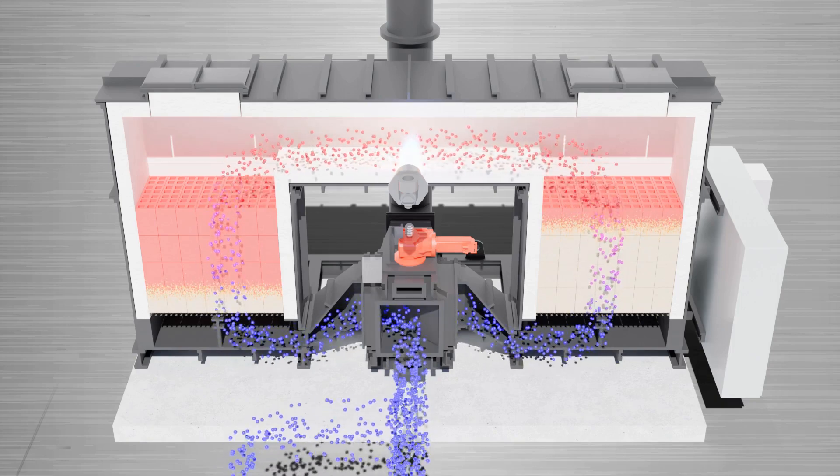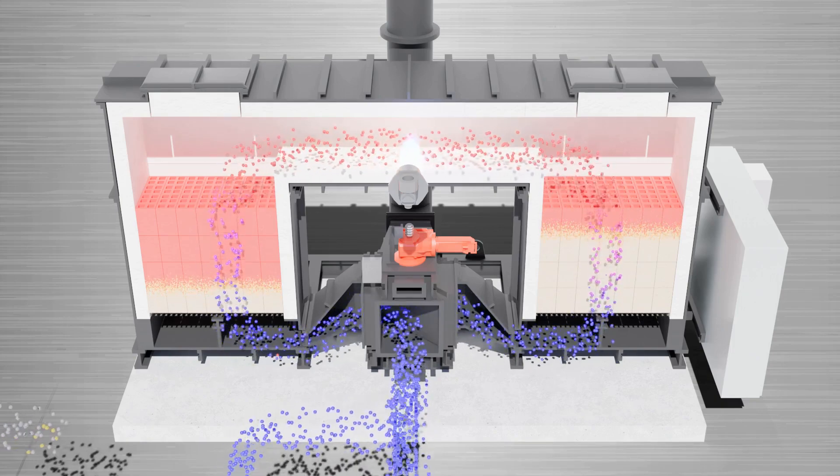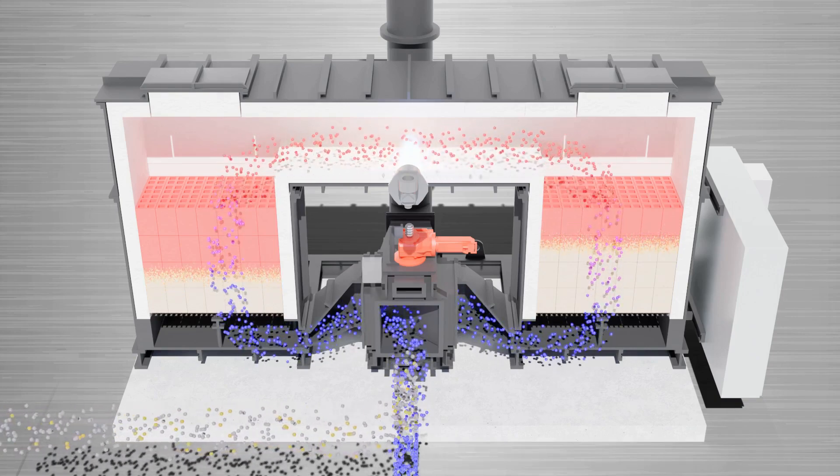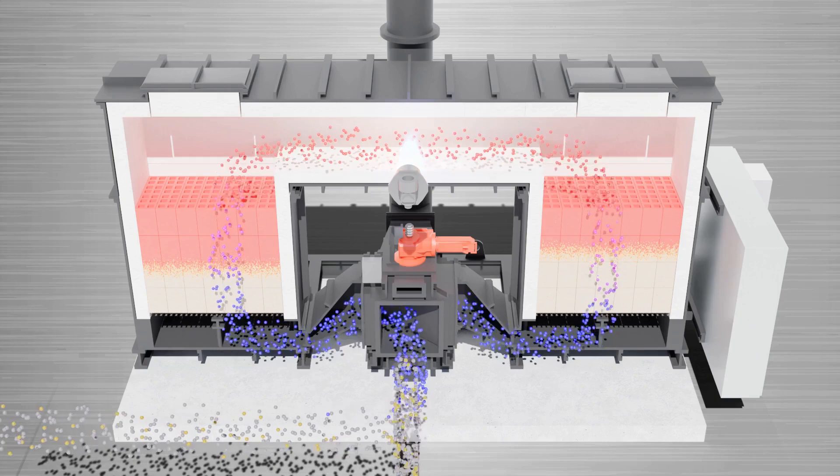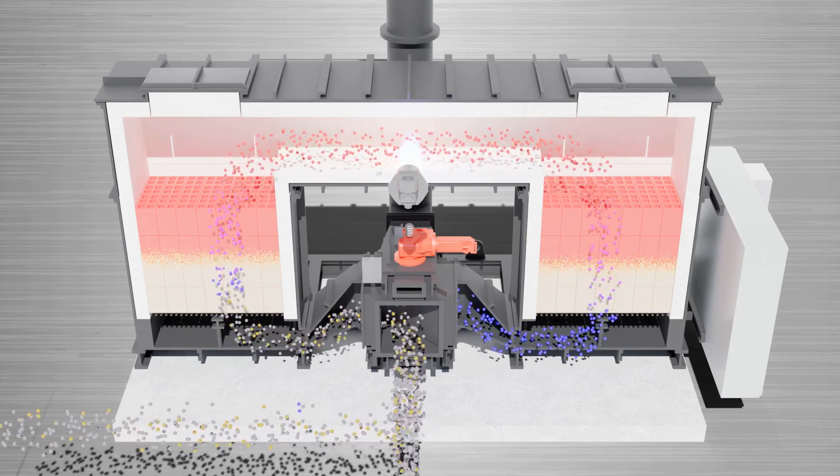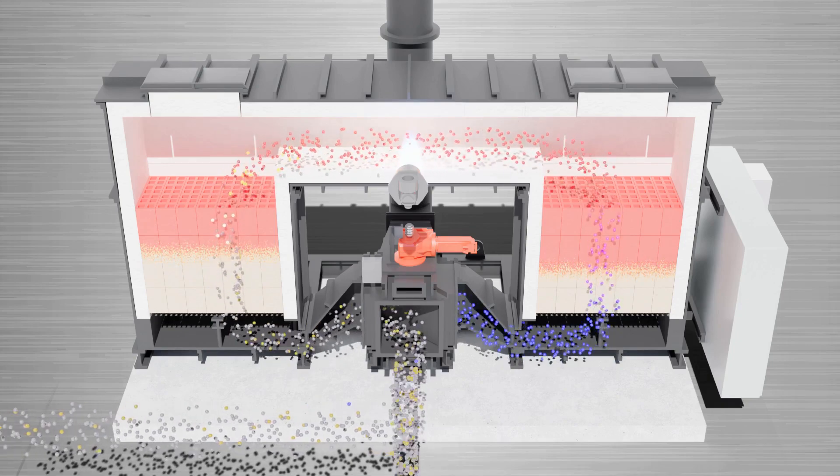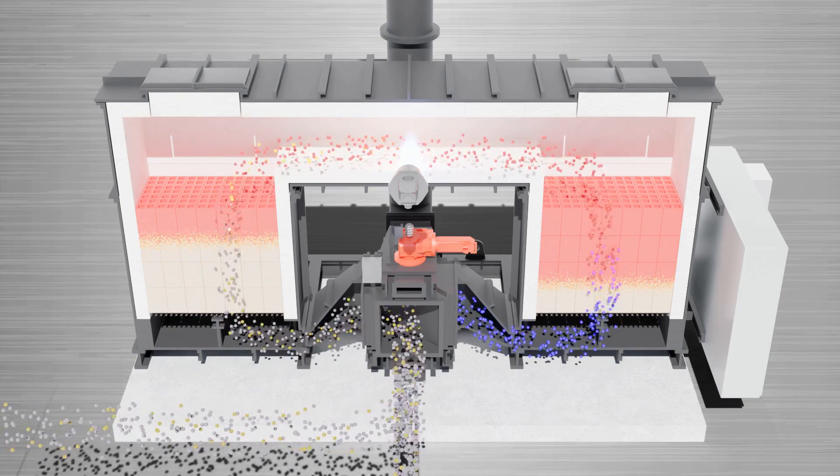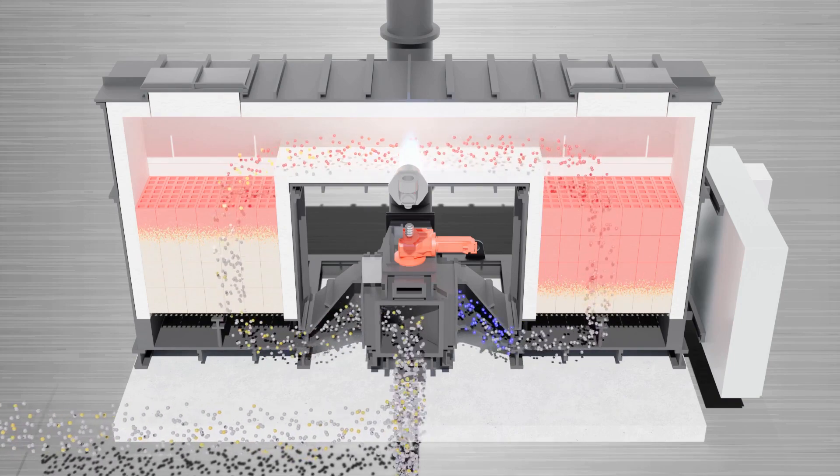Once the system has equilibrated and all safety interlocks are met, the process blocking damper is permitted to open. The system is now in normal operating mode. The waste gas is preheated by the left bed. The contaminants shown in yellow are destroyed in the oxidation chamber. Heat from the products of combustion is recovered in the right bed.